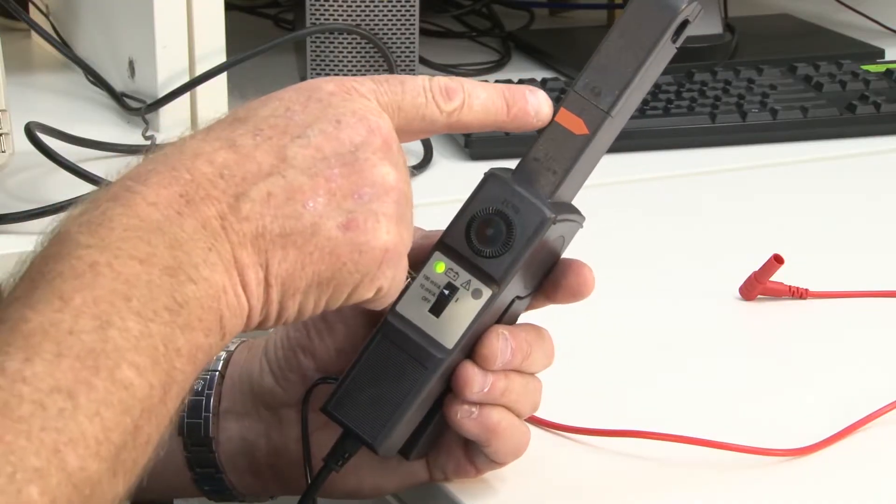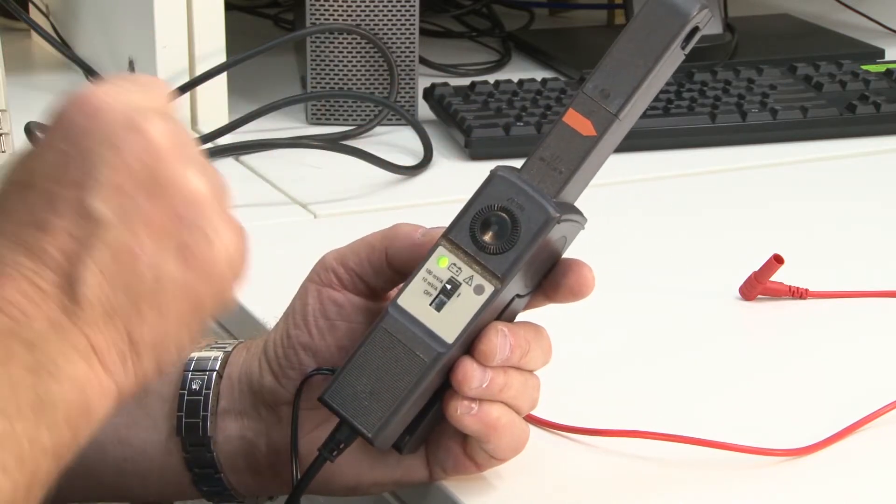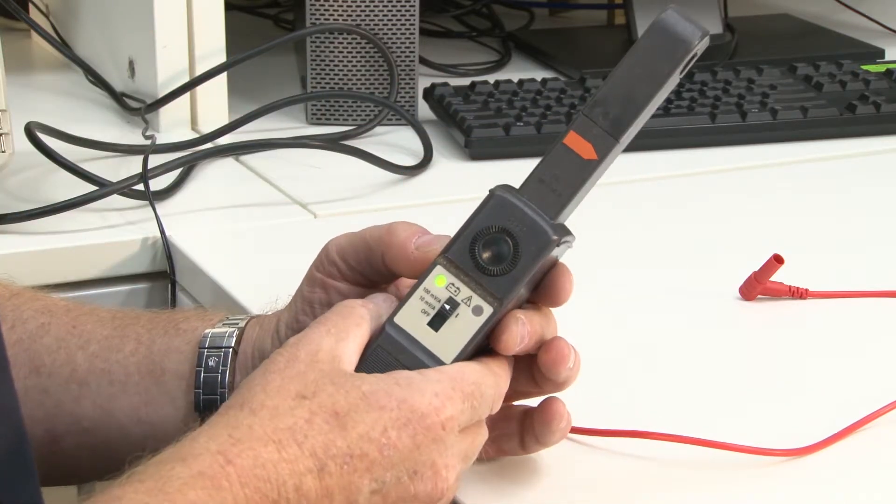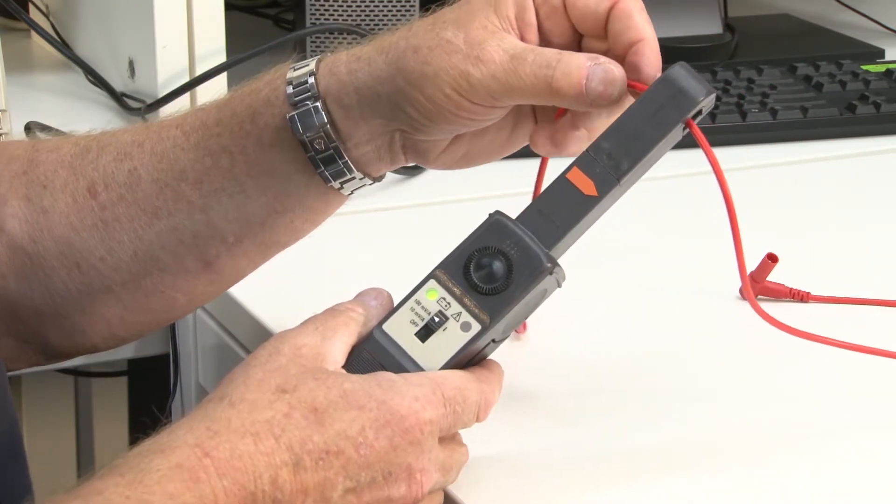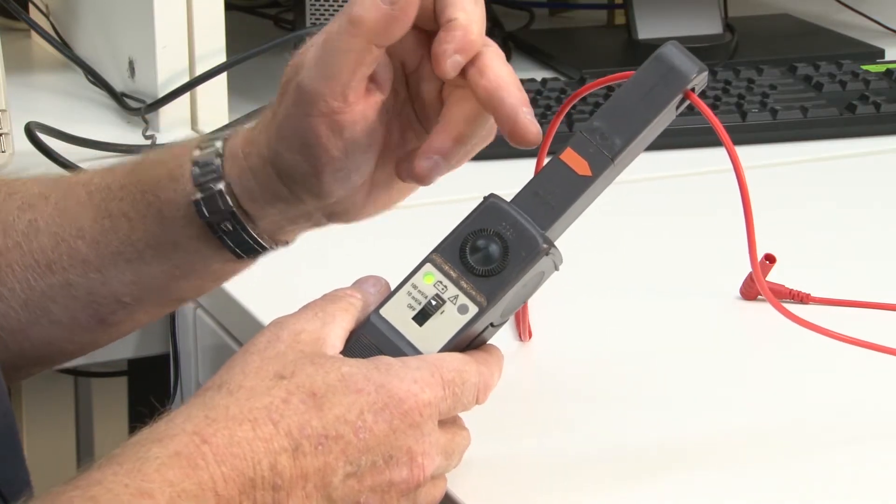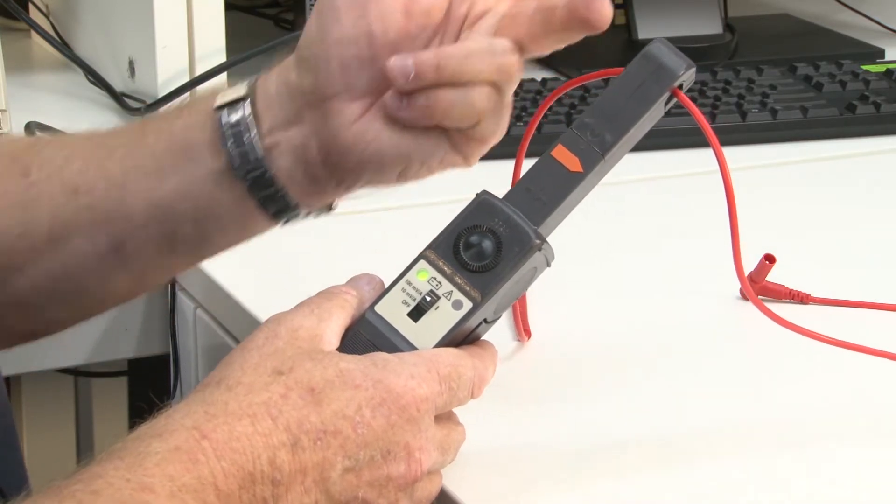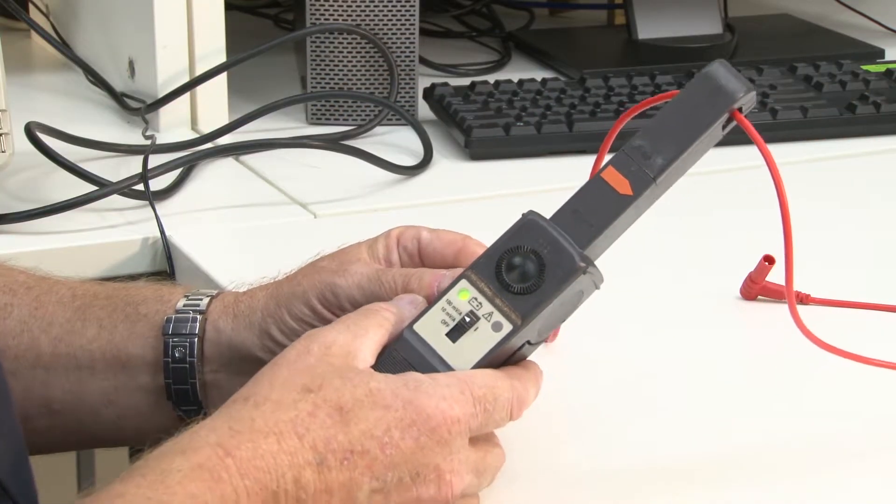The first thing you'll notice here is that we have a little arrow here. Now this is a clamp-on device. So if we have a cable such as this, we simply clamp it around the cable like so. But what we need to make sure is that this probe is connected with that arrow in the same direction of the actual current flow. So it's important to actually do that.